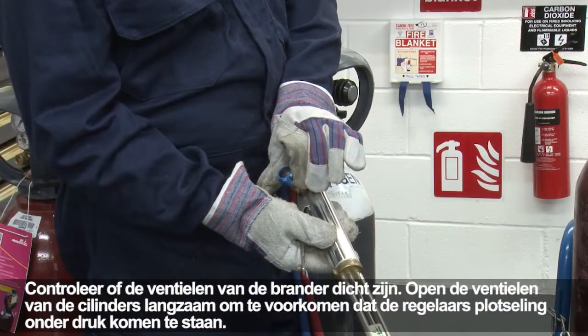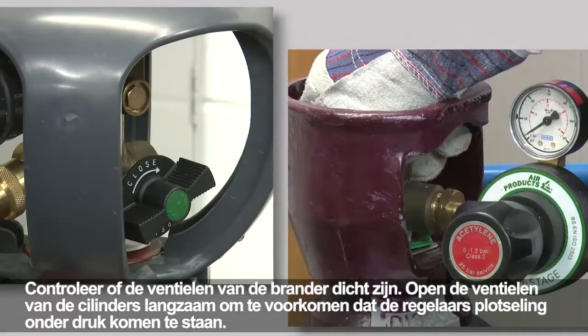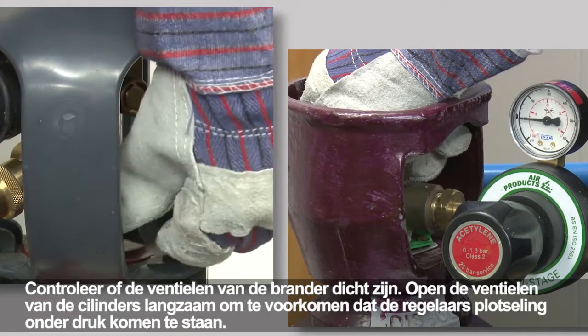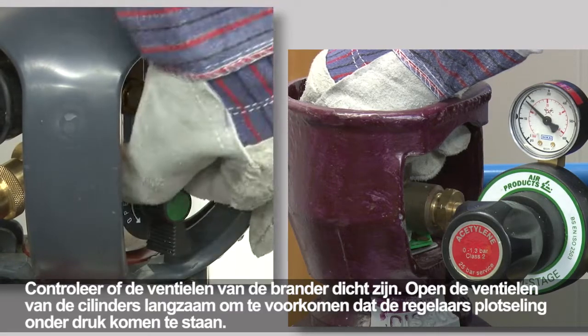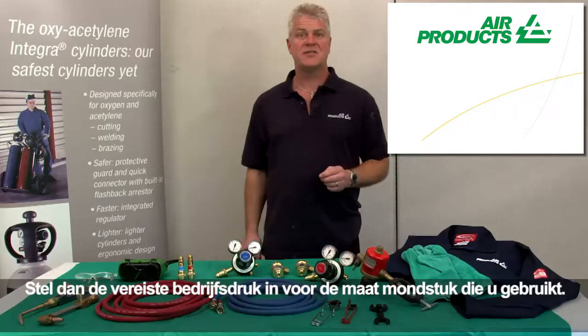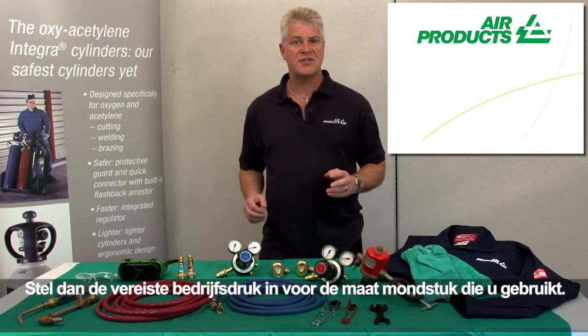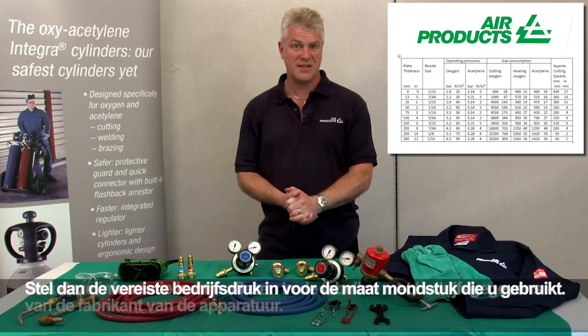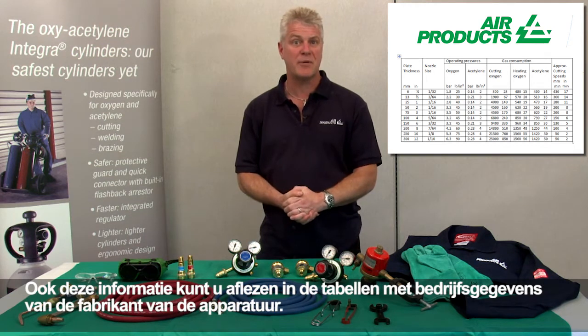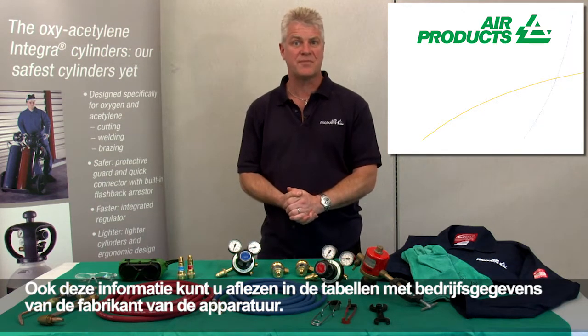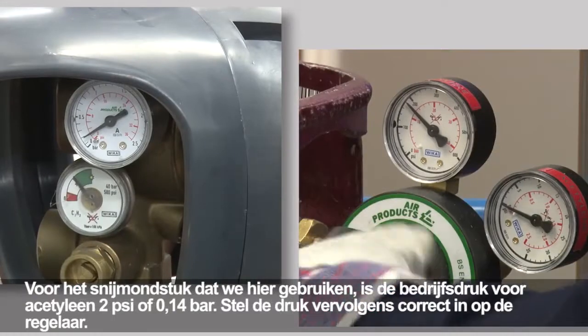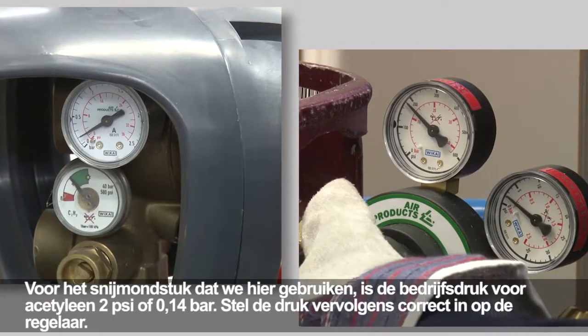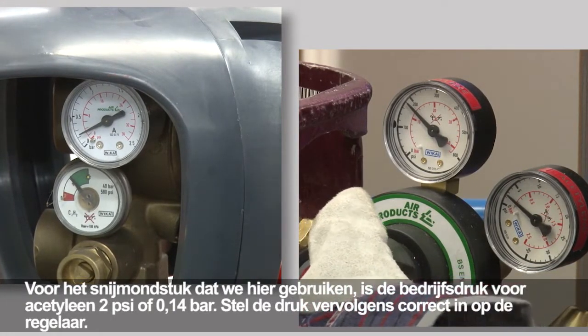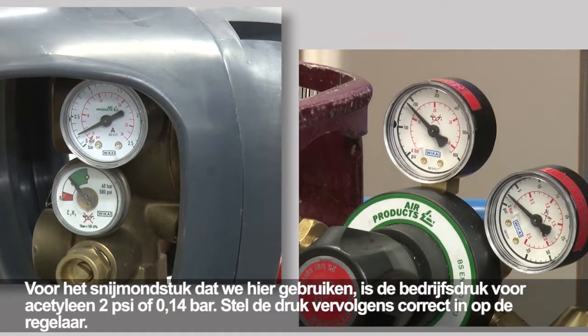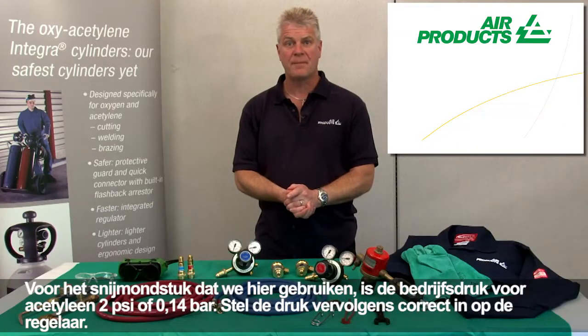Check that the torch valves are closed. Open the cylinder valve slowly to avoid the sudden pressurization of the regulators. Next, set the required operating pressure for the size of the nozzle you're using. This information can be obtained from the equipment manufacturer's operating data tables. For the cutting nozzle we're using here, the operating pressure for acetylene is 2 psi or 0.14 bar. Then adjust the regulator pressures accordingly.